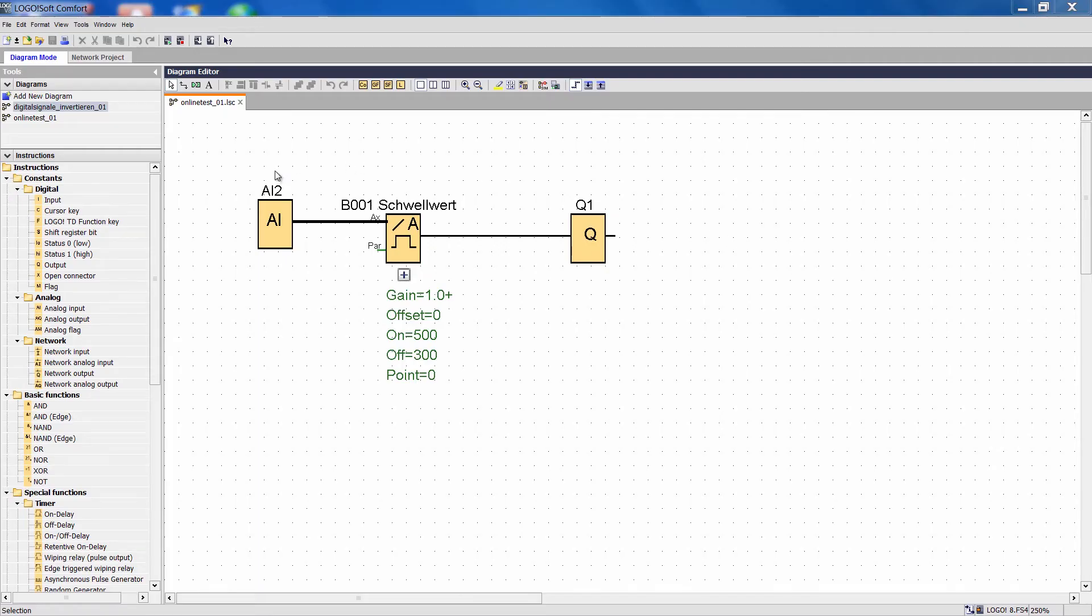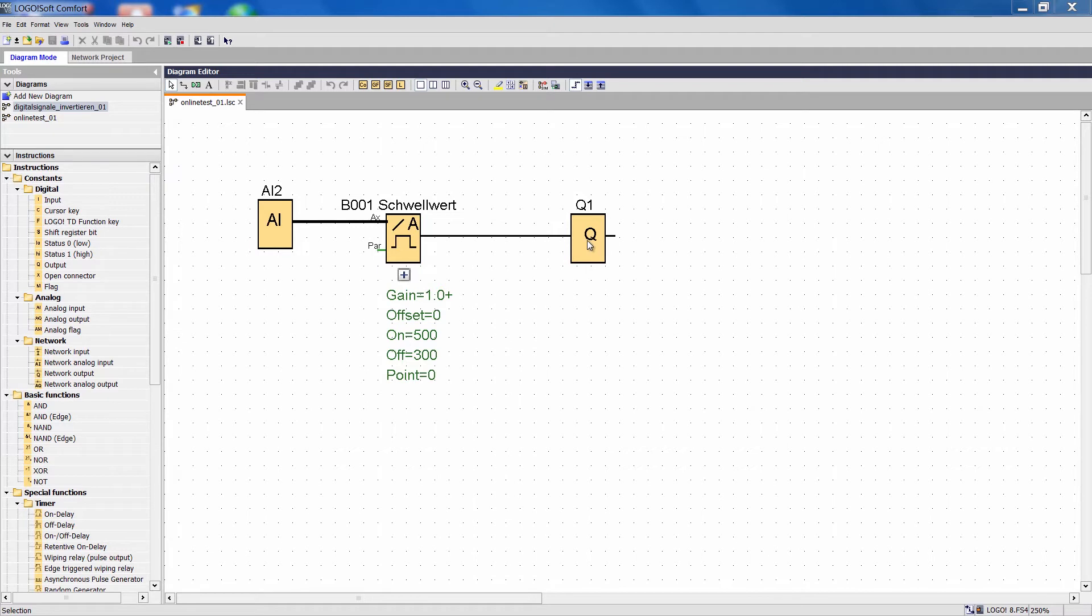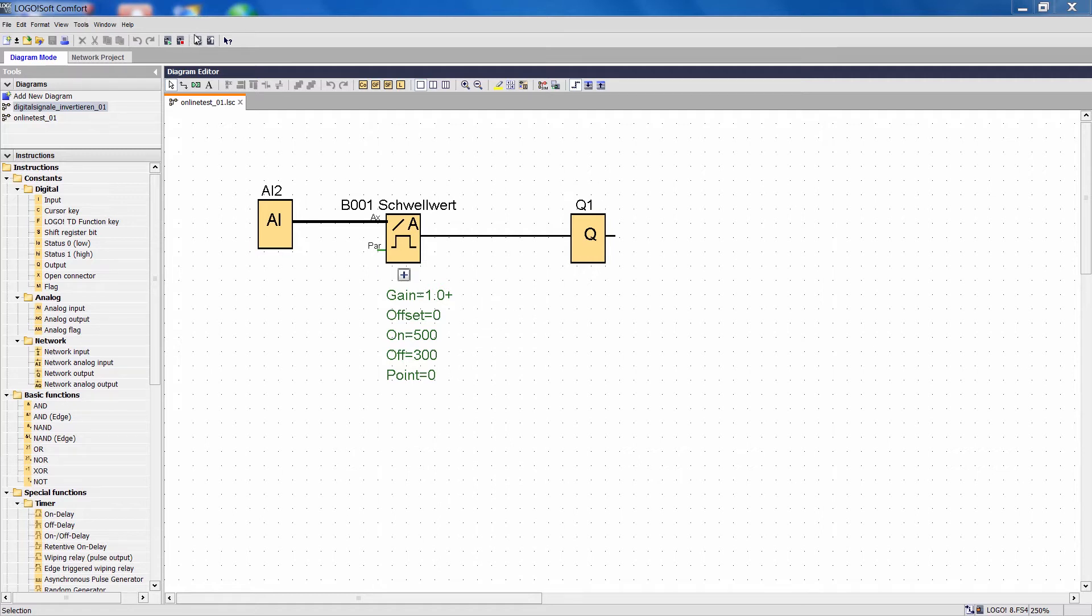This is a program that allows an evaluation of the analog input 2 via a threshold switch that switches output Q1. In my settings for the threshold value I set 500 as my activation threshold and 300 as the deactivation threshold.